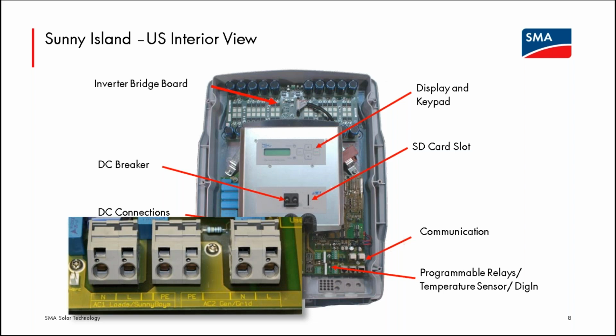To the lower right, you see a red arrow for communications and the relays and temperature sensor and dig-in. Dig-in is something I'm not going to spend time talking about, but it is important and must be wired if someone is using the system for grid-tied backup with a generator. Dig-in tells the Sunny Island when that external switch has changed the AC source from the grid to the generator. It actually changes some operating parameters in the Sunny Island, so it is required for that install.